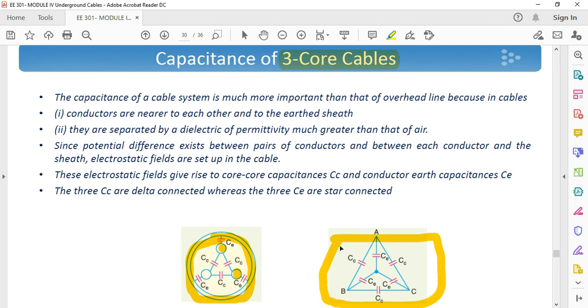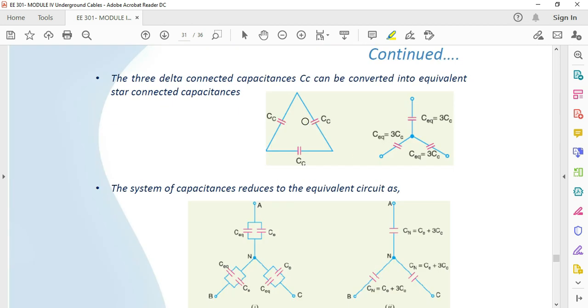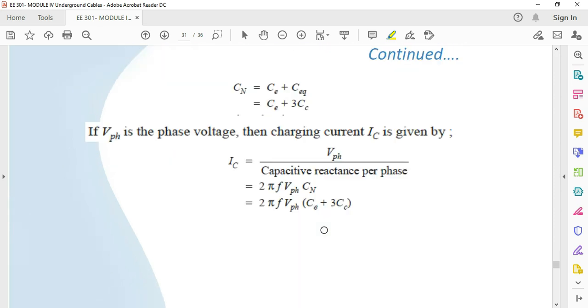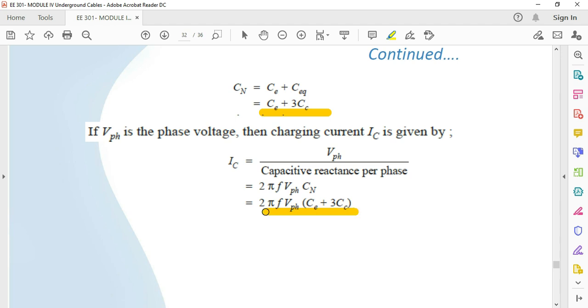The equivalent circuit can be drawn, and we can convert the delta-connected CC into star. The equivalent capacitance from delta-to-star conversion is 3CC. So the total equivalent capacitance per phase in star connection is CN = CE + 3CC. If Vphase is the phase voltage and IC is the charging current, then IC = Vphase / (1 / 2πf·CN) = 2πf·Vphase·CN, where CN = CE + 3CC.